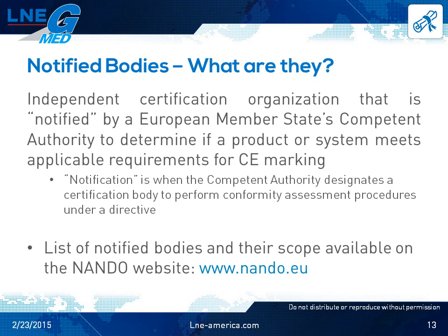Not all notified bodies are notified to be able to perform conformity assessments for medical devices. Instead, some notified bodies may focus on things like construction products, or toys, or communication devices, or other items that also have their own directives. The notified body will tell you if it's not notified for your product or a specific conformity assessment.